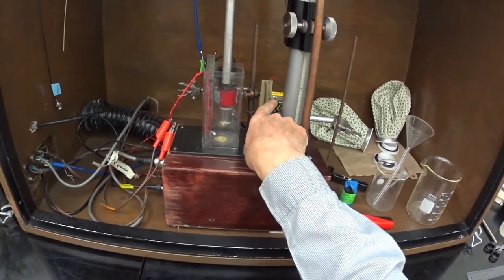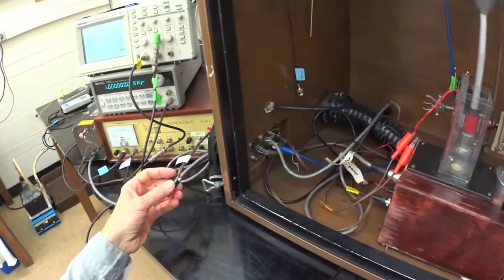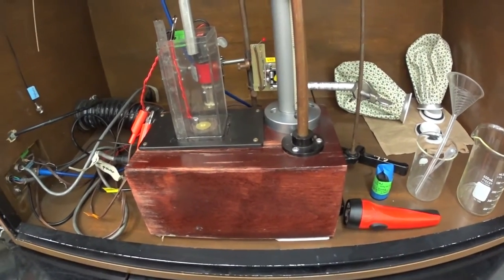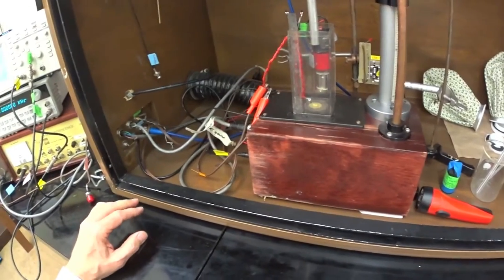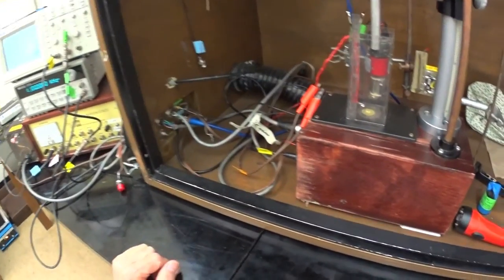The other thing you can see here is an LED flasher, which we can make flash using this LED trigger button here. It's a very faint red glow when I press the button. We're going to use that to make sure the photomultiplier tube is working. So our heater's connected. All the other wires have been connected already. If not, you will have to connect them up to figure out what's going on.